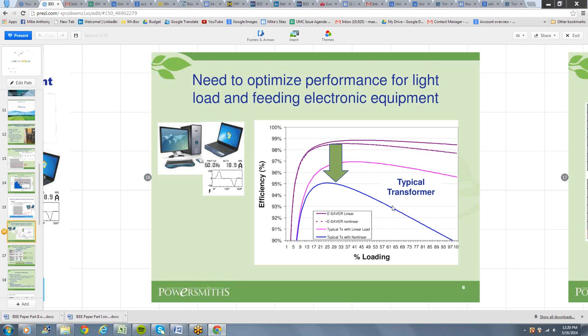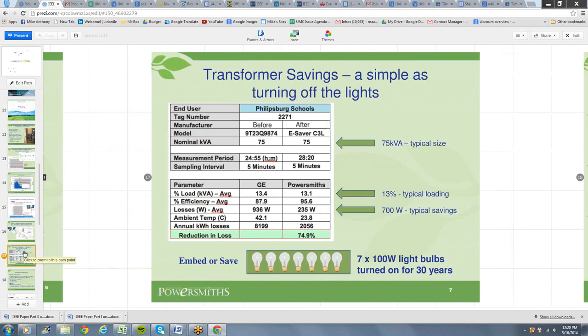So the right kind of transformer for the modern application is a transformer that, first of all, has a rating for that nonlinear load. The second thing is it's got to address the light loading reality, so it's got to peak at efficiency very, very quickly. As you can see, that's what we're getting at the top here. The next thing you've got to look at is, okay, I'm not feeding light bulbs, I'm feeding electronics, and I've got to minimize those incremental losses. I don't want this giant gap that I see with a typical transformer. I want to narrow that. So that's really the combination you're looking for. And what that means is shown on the next slide.